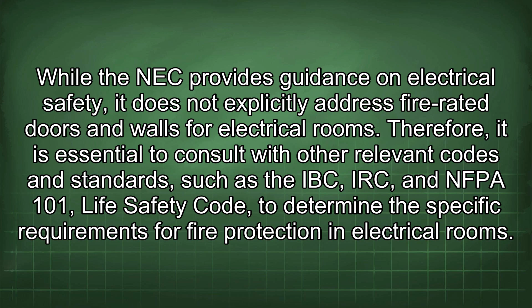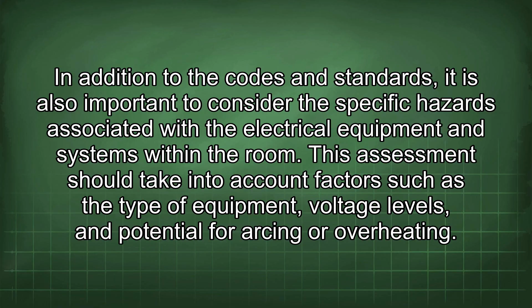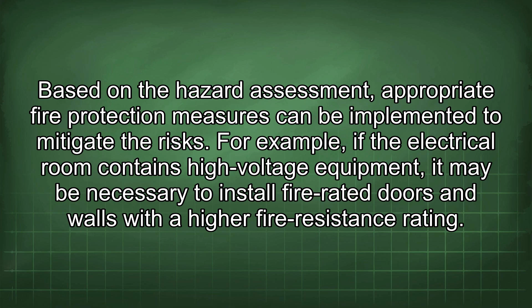In addition to the codes and standards, it is also important to consider the specific hazards associated with the electrical equipment and systems within the room. This assessment should take into account factors such as the type of equipment, voltage levels, and potential for arcing or overheating. Based on the hazard assessment, appropriate fire protection measures can be implemented to mitigate the risks. For example, if the electrical room contains high voltage equipment, it may be necessary to install fire-rated doors and walls with a higher fire resistance rating.